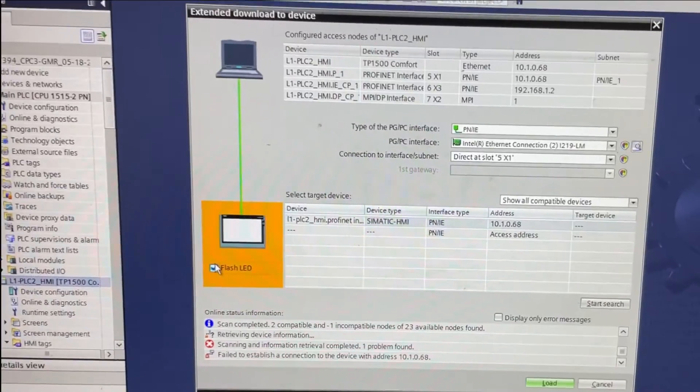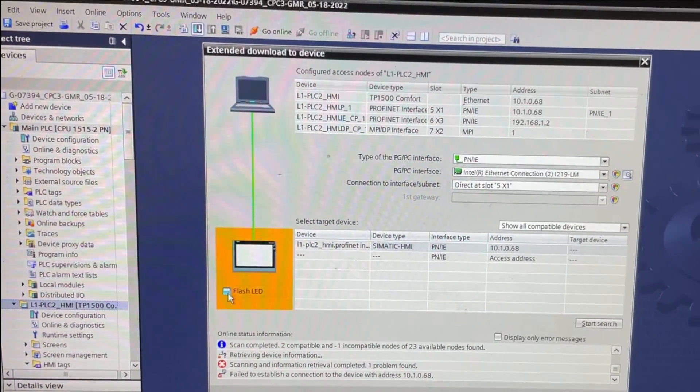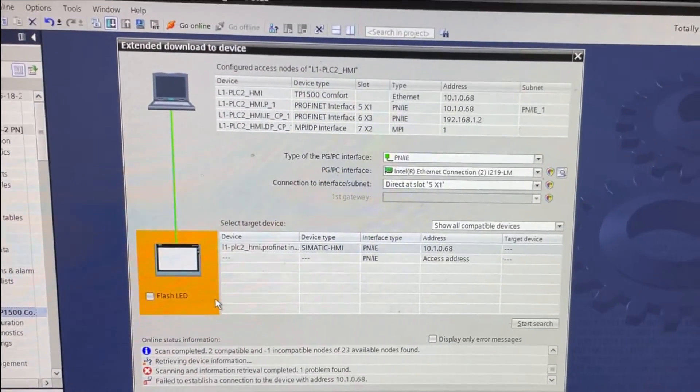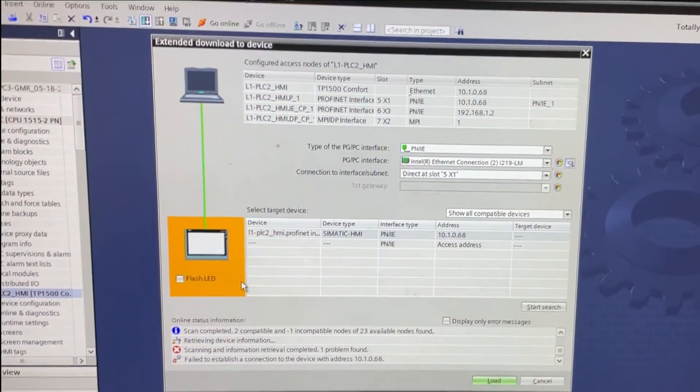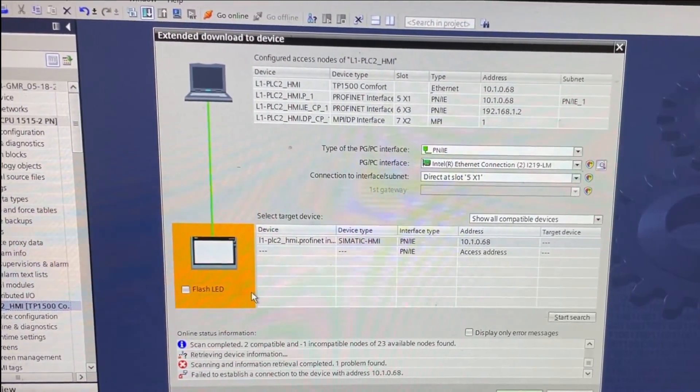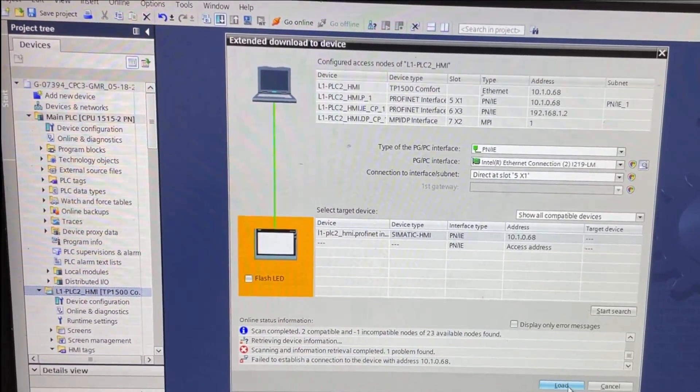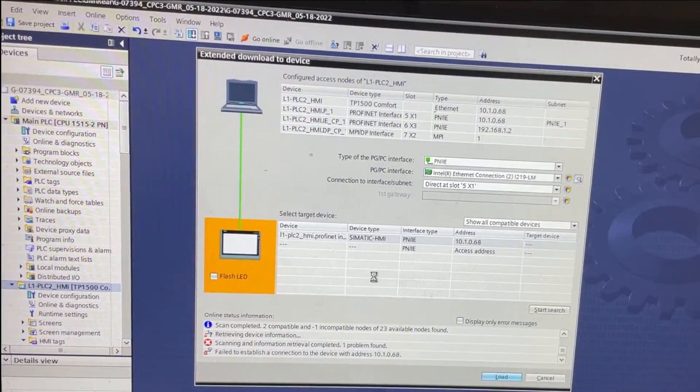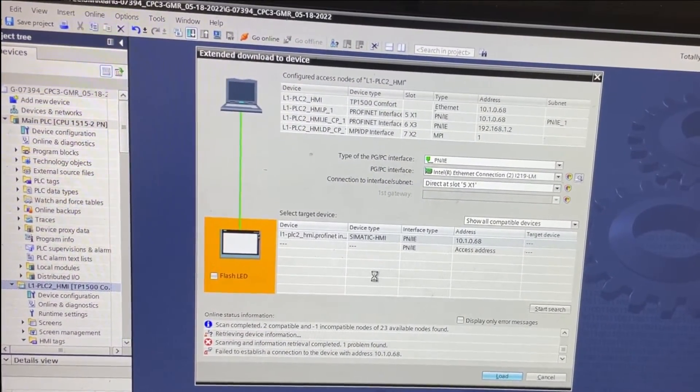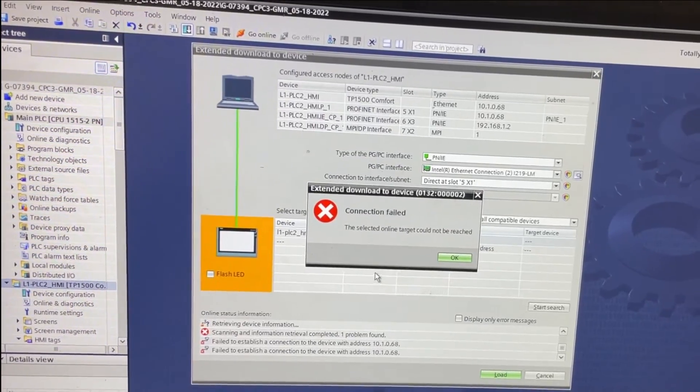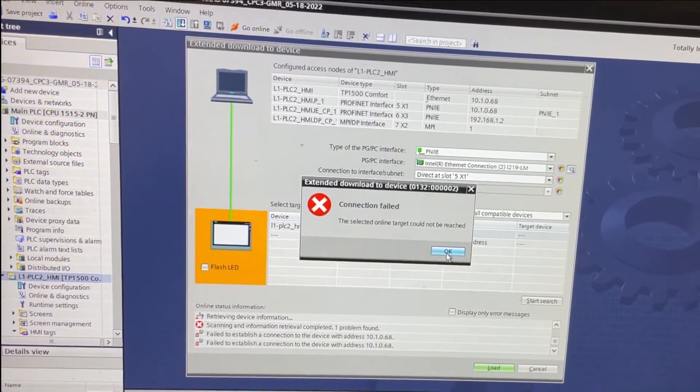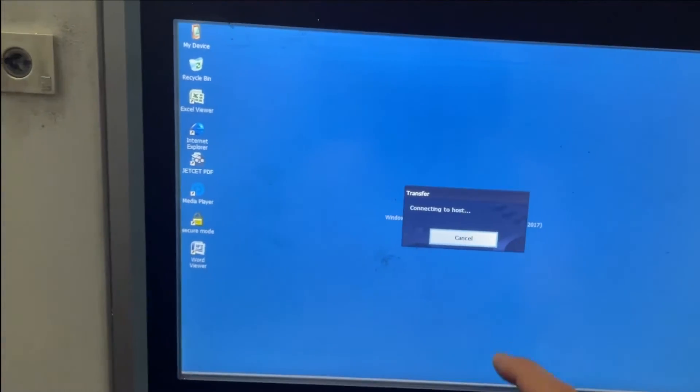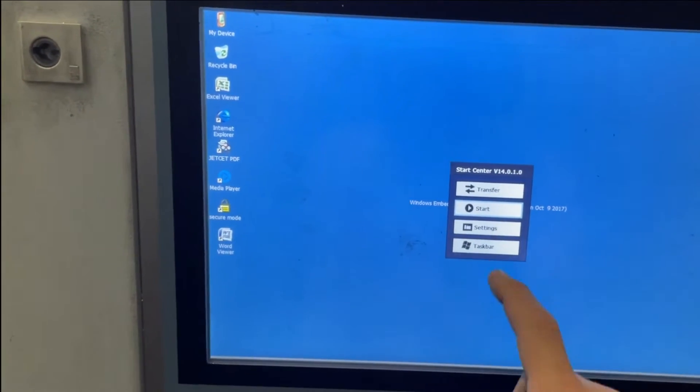I was watching the HMI where I noticed that it was changing, but still, after that, whenever I go to load, it still doesn't load the application to the HMI. The solution I found was that I did not configure correctly in settings under transfer settings.